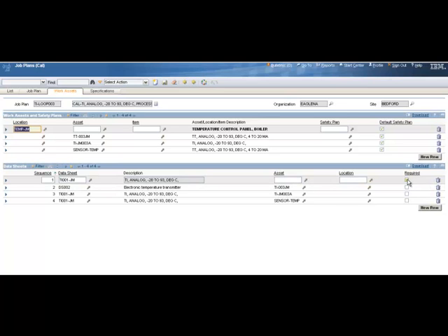And we'll see in a little while when I do the work order for this that on the data sheet at the work order level, if I perform a calibration on the loop itself and those points are okay and it passes, I don't have to do the remaining data sheets. They're optional. But if the loop fails its calibration, then I have the other remaining data sheets there on the same work order. I can do each one, calibrate each individual component, and find a defective one much faster that way.